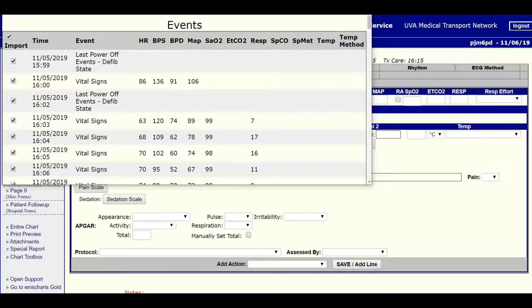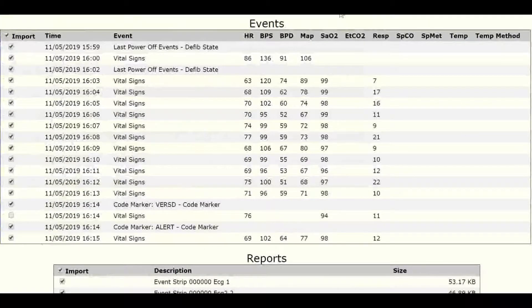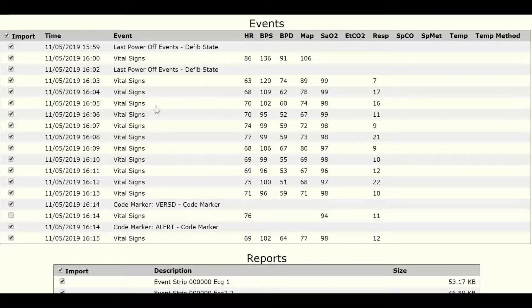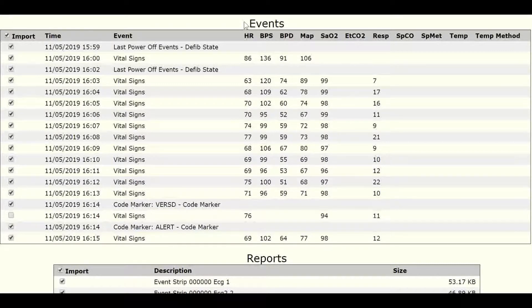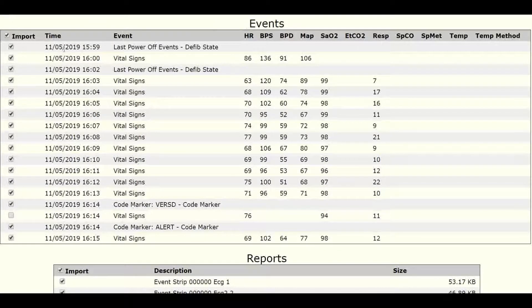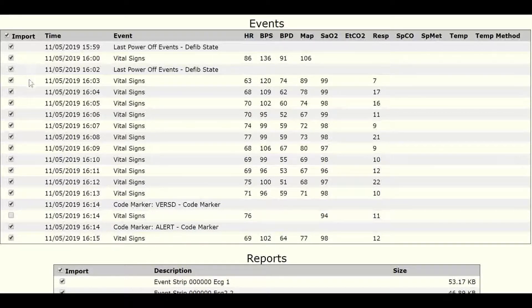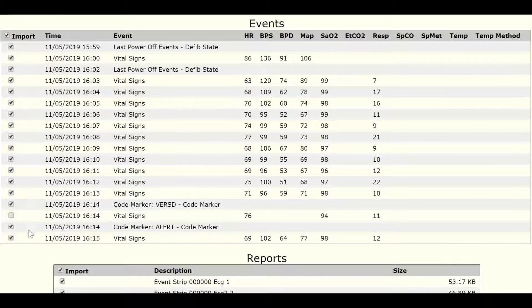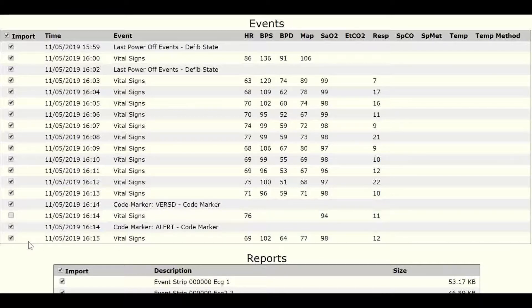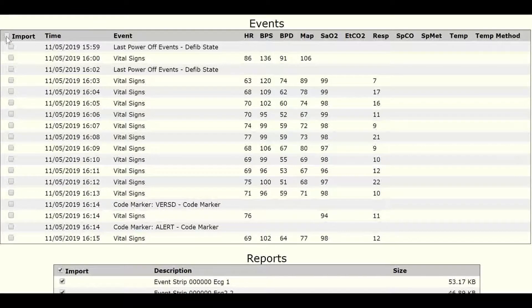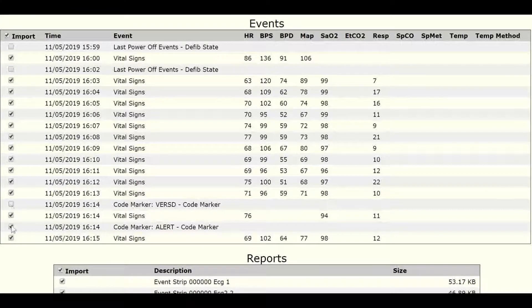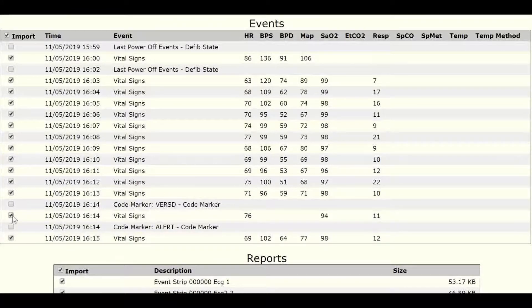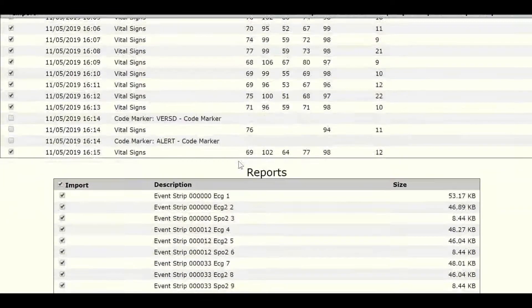Here you'll be presented with two blocks of information. The top is called Events, and has to do with anything you may have inputted into the monitor in terms of the vital signs, power on, power off, as well as any markers you may have done during the call. There's often a lot of these, and maybe some ones that you don't want, so you can selectively add or delete them for the import, and I recommend you do that.